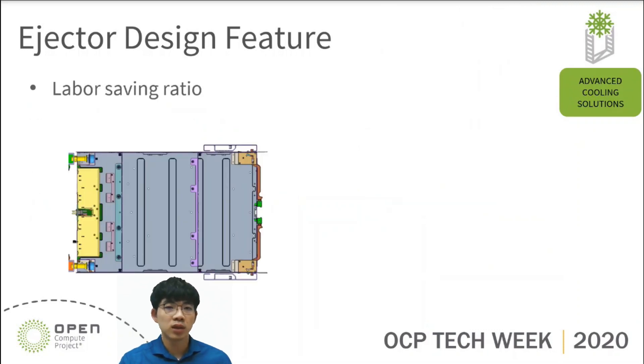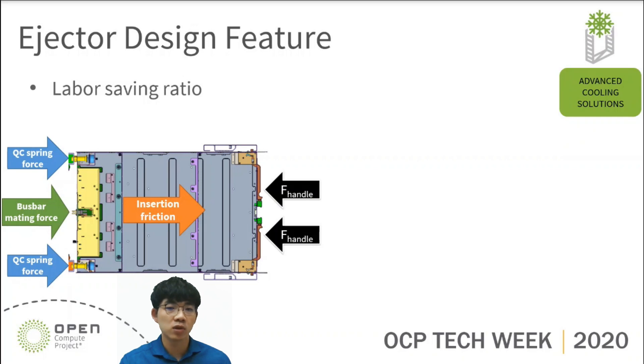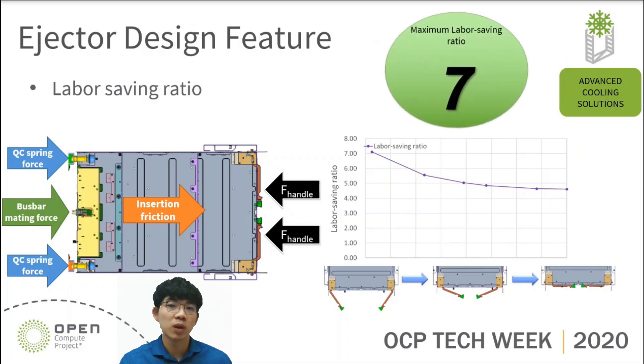Let's talk about the last ejector design feature: labor saving ratio. To calculate the labor saving ratio, we should consider the QC spring force, busbar mating force, and insertion friction between IT gear and the rack. The force on the handle should overcome these forces so we can use the ejector to install IT gear into the rack. On the right, we use the principle of lever to calculate the labor saving ratio. The labor saving ratio will change accordingly throughout the installation process of IT gear. In the current design, the maximum labor saving ratio is up to 7. We think this ejector can lighten the operation force effectively. These are all of the ejector design features we would like to share.